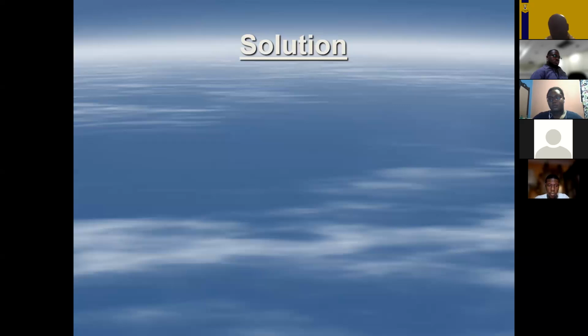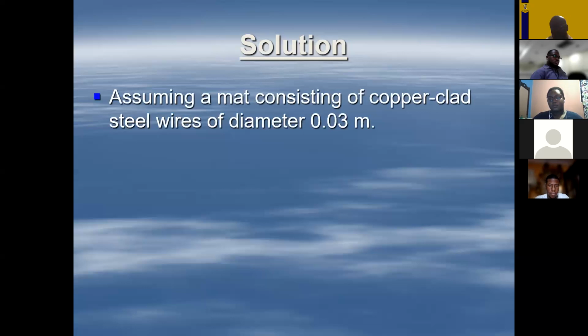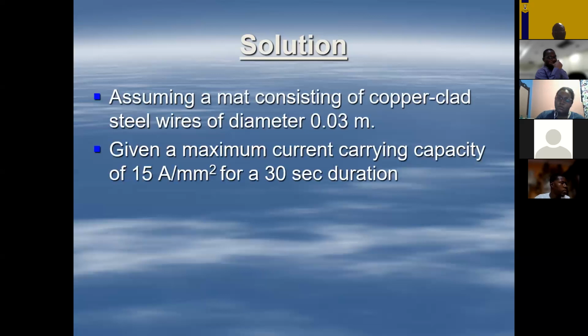So this example, what we are saying is, okay, let us say that we are using copper clad steel wires, and this is the diameter, all right? And these have a maximum current carrying capacity of 15 amps per square millimeter, and that is up to a 30-second duration, right? You can then look in terms of the time that we were considering. The maximum time was 250 milliseconds, yes?